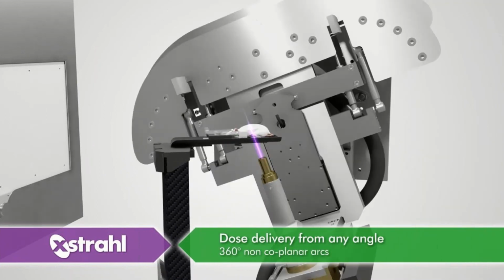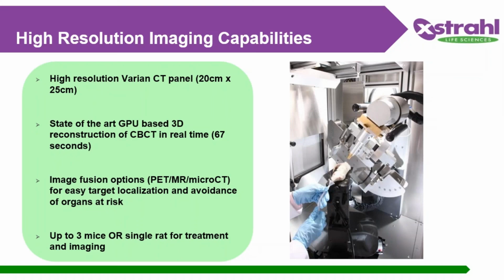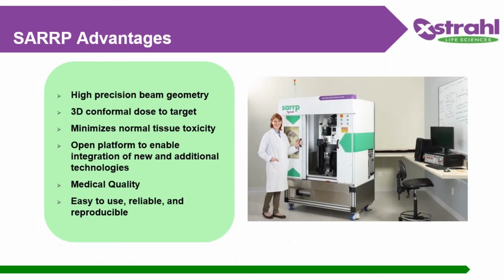We acquire a CT through a pancake geometry, which means the detector and the X-ray tube are static and the animal moves in the theta circular direction during exposure. We found that we get better spatial resolution with this setup compared to a tubular geometry. Here's a picture of 3 mice lying down on a bed prior to cone beam CT acquisition. As I mentioned earlier, a CT acquisition takes only 67 seconds, and its volume reconstruction is done in real time.